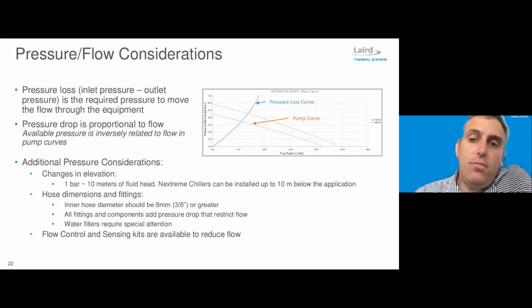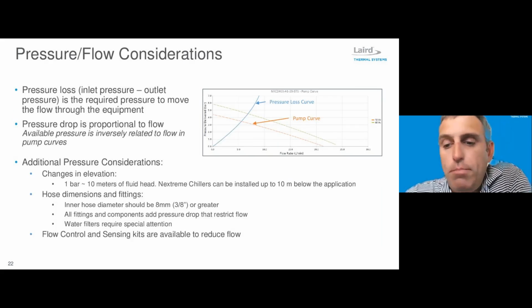So there's a couple of things that we need to keep in mind when we size pumps within chillers. The pressure loss of the system, so this is the inlet pressure minus the outlet pressure. So this is what's required in order to move the flow through the instrument or through the application. The pressure drop within a system is proportional to the flow.